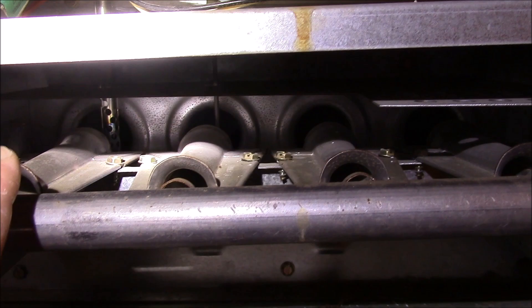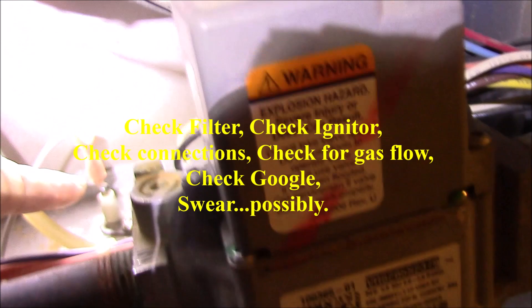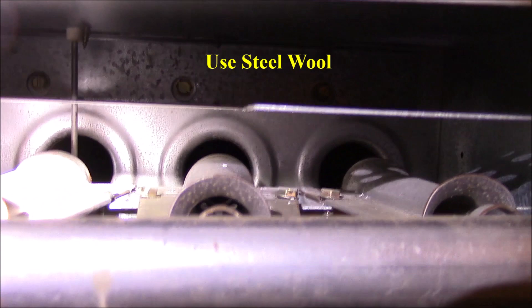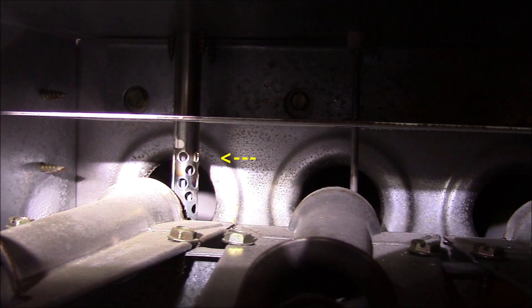So what I did was a whole bunch of things. I took out and cleaned — you can actually see it from up here — right there is the flame sensor. I took that out and cleaned it because it can get gunky and then it doesn't read if there's a flame. But I wasn't even getting that far — what's supposed to happen is that right there is supposed to ignite, and it wasn't even getting warm.